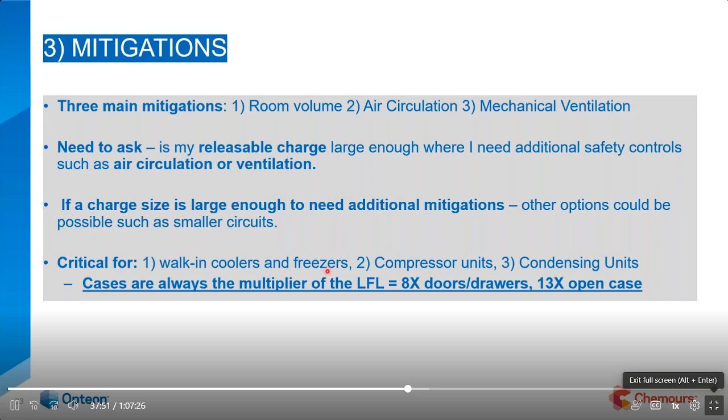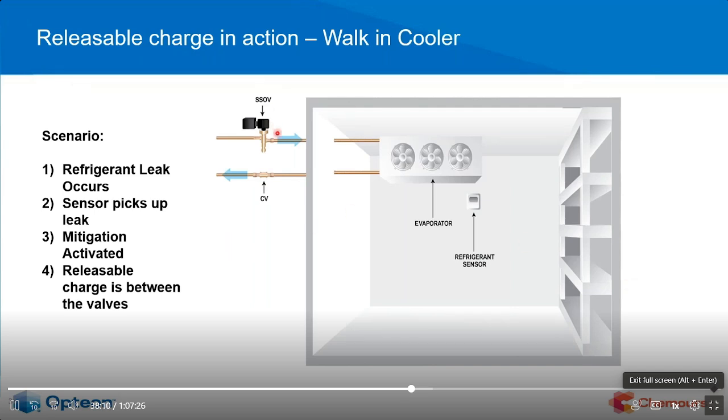Critical for walk-in coolers, compressor units, and condensing units. The cases, I wanted to point this out. I actually put this in caps earlier this morning and underlined it. Cases are always the multiplier of the LFL, 8 times for doors and drawers and 13 times for open case. All right. So let's look at this walk-in cooler, if you will.